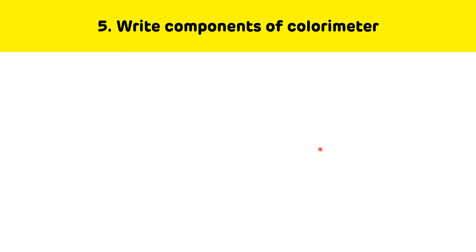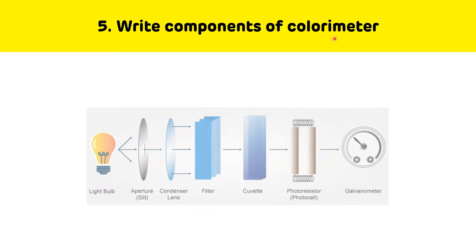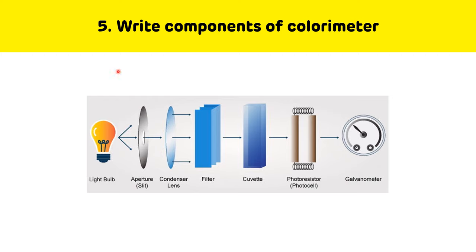Fifth question: write the components of the colorimeter. The components of the colorimeter are: light bulb, slit, condenser lens, filter, cuvette, photoresistor, and galvanometer.